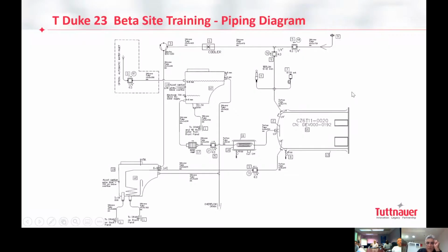Okay. So this is the piping diagram. What I said before regarding the automatic water inlet is optional. There is a float switch, another float switch here, and a solenoid valve, and by the level here, if it senses that there is no water, this one opens and water automatically fills into the tank. There is a chamber and two water tanks. They are together in the top, but they are two. It's one piece of plastic, but there are actually two tanks. One is the mineral-free or clean water we are using for generating the steam. The other one is the waste tank, which can also be connected from the back directly to the drain by using this, one second, this one.